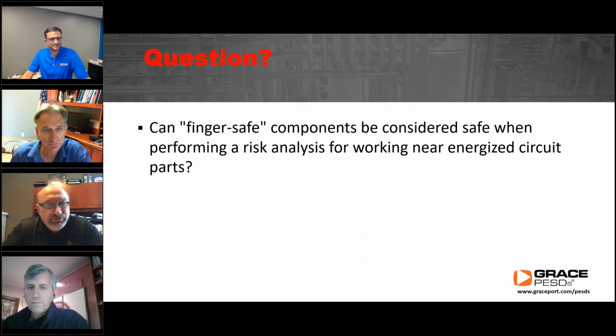So you have to do an arc flash risk assessment and a shock risk assessment. And if it's completely insulated with finger safe guarding, or insulated conductor circuit parts, you still may have an arcing fault and arc flash risk related to the work task.